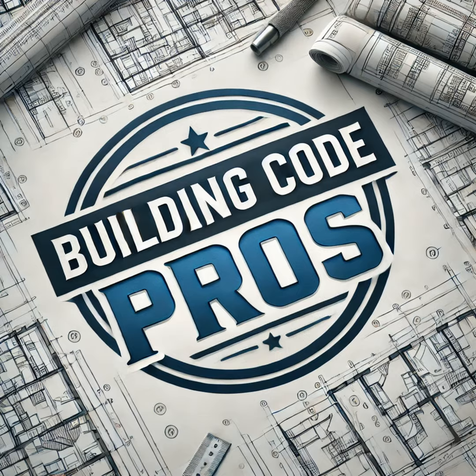Absolutely. And my final one, maybe the unsung hero. Don't forget about fire blocking under R302.11. Pay attention to the parts of the house you won't see once the drywall goes up. Just remember the basic rule. Fire blocking needed vertically at floor and ceiling lines and horizontally every 10 feet inside those hidden wall cavities. That's your primary internal defense against rapid fire spread.